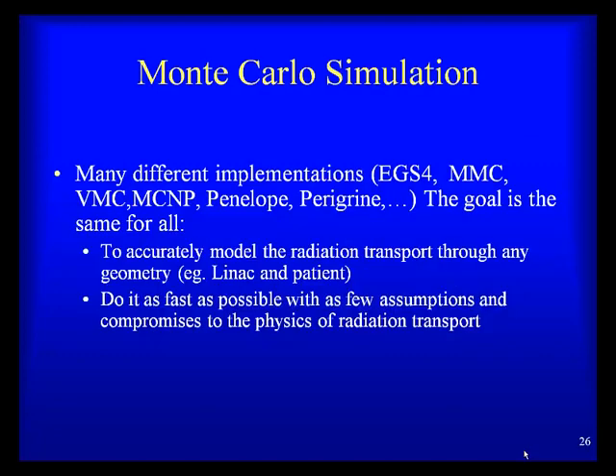There are many different flavors of Monte Carlo algorithms — EGS4, MMC, VMC, MCNP, Penelope, Peregrine — but they all share the same goal: accurately model radiation transport through any geometry, including the linear accelerator and the patient, as fast as possible with as few assumptions and compromises to the physics of radiation transport, maintaining accuracy to the extent that is clinically relevant.